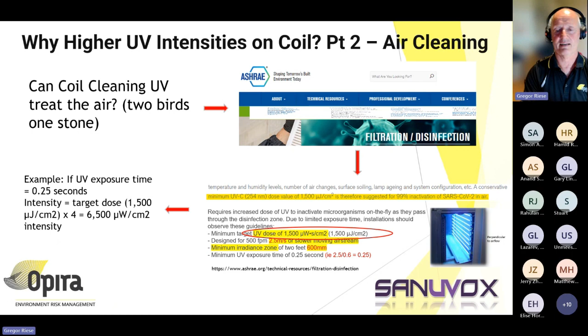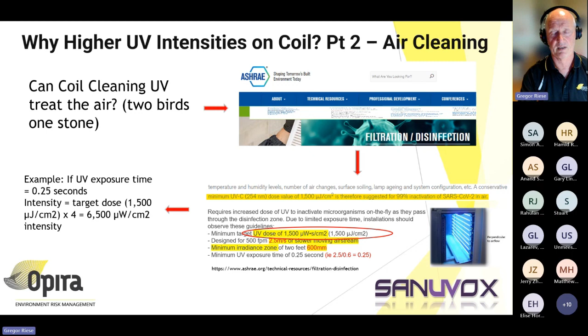inactivation of COVID, I've just done the math there and I won't go through it, but you need 6,500 microwatts per centimetre squared on that coil, which is more than 10 times, probably near 15 times what we recommend to put on a coil. But here the customer is asking for air disinfection. So you think, well, okay, let's put high power on the coil and achieve some degree of air disinfection.